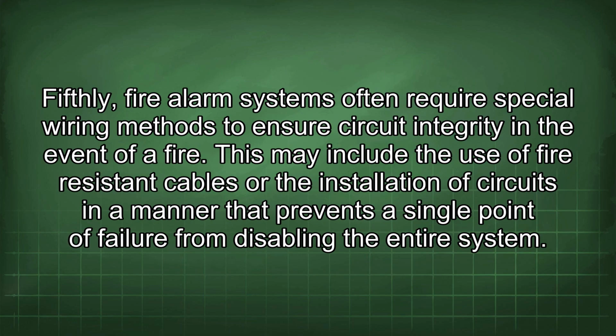Fifthly, fire alarm systems often require special wiring methods to ensure circuit integrity in the event of a fire. This may include the use of fire-resistant cables or the installation of circuits in a manner that prevents a single point of failure from disabling the entire system.